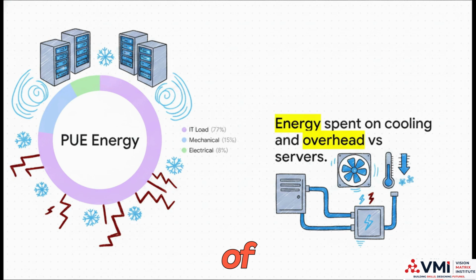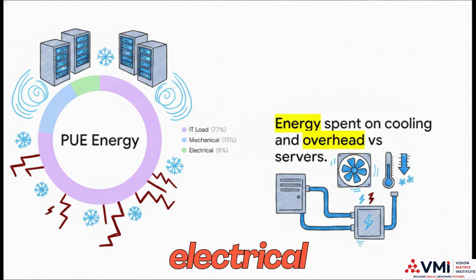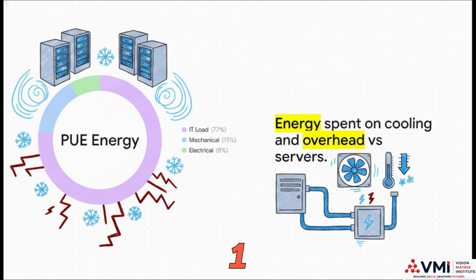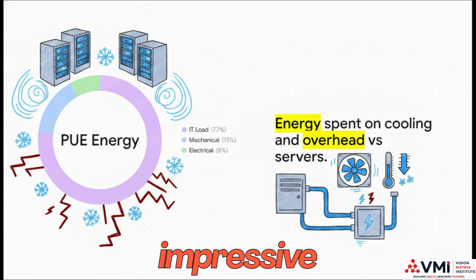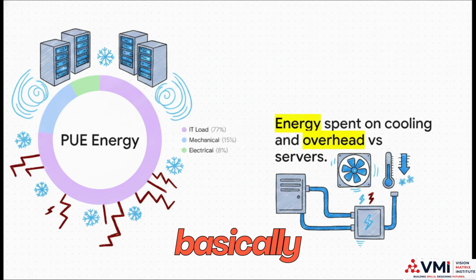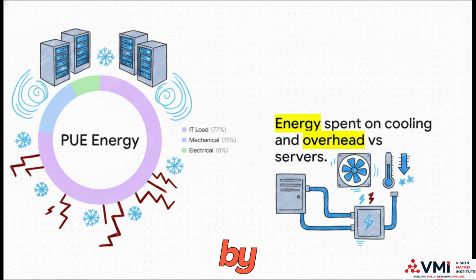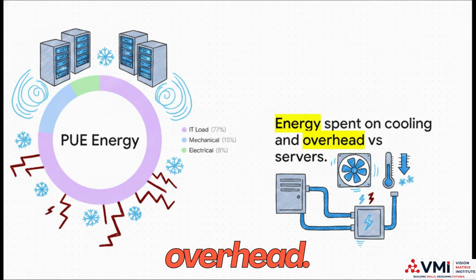Surprisingly, a huge portion of the power coming from the grid isn't doing computer processing at all. It's spent running massive chillers to stop the servers from melting, and overcoming the natural electrical resistance in the wires. Getting a PUE score down to 1.3 is considered highly impressive in the industry - that basically means for every 1 watt used by the server, only 0.3 watts are spent on cooling and overhead.